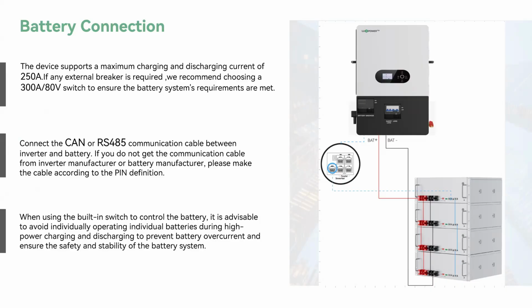And we have both CAN and RS485 communication supported. So we have to connect the cable between the inverter and the battery. If you don't have the cable that came with the manufacturer, please make the cables according to the pin definition, and I will talk about the pin definition later. And when using, for example, the built-in switches of the batteries, we do not recommend you to turn off the individual batteries, to prevent overcurrent when the battery is in high power charging or discharging.